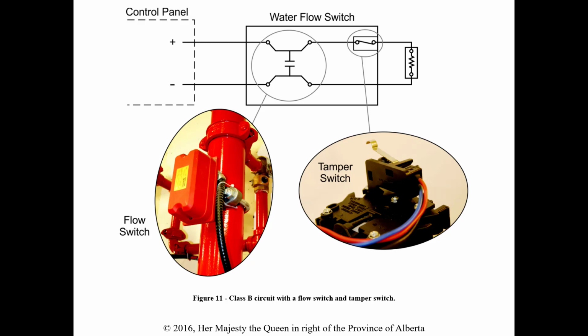Then it talks about tamper switches. So there's portions of the fire alarm system that, if it's got a sprinkler system, it'll have valves, it'll have potentially a sprinkler tree attached to it, all that kind of stuff. We have to know if that's operational.